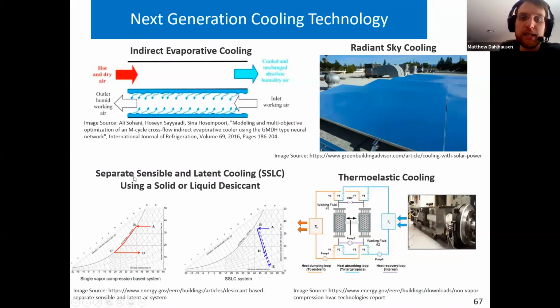There are a variety of newer cooling technologies at various phases of commercialization. Indirect evaporative cooling, here in the upper left, works by spraying water into the air, cooling it down, and then running it through a heat exchanger to cool down the incoming airstream. This can only provide sensible cooling, but does so very efficiently and can meet cooling needs in dry climates. Radiant sky cooling uses selective materials to reflect incoming short-wave solar radiation, but stays open to long-wave thermal radiation, allowing radiant heat rejection to the sky. These panels can cool down a working fluid to 10 to 15 degrees Fahrenheit below the ambient temperature. Both of these are commercialized technologies increasingly used in current building projects.